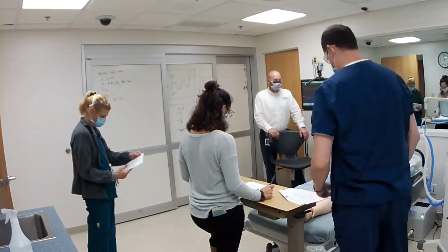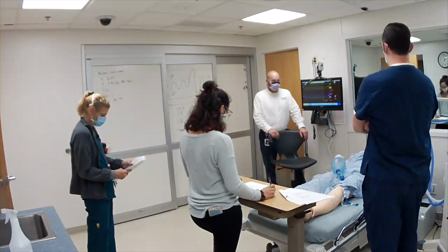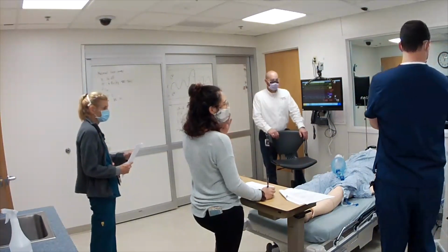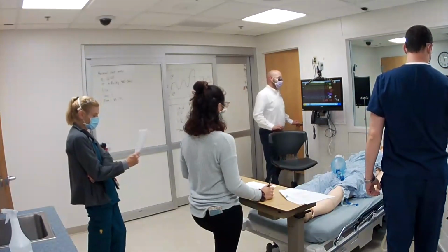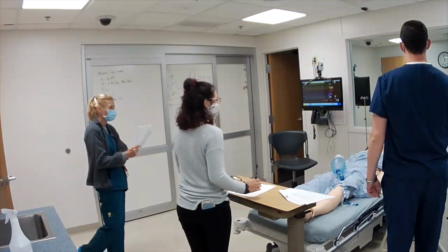Set the ventilator to 280 and a rate of 7. Okay. So we're going to turn our ventilator way down. You actually want me to turn this, or? Yep. 280 and a rate of 7. Okay.